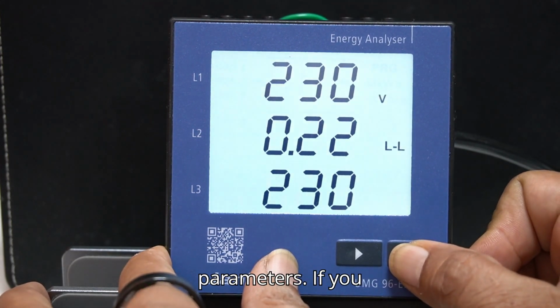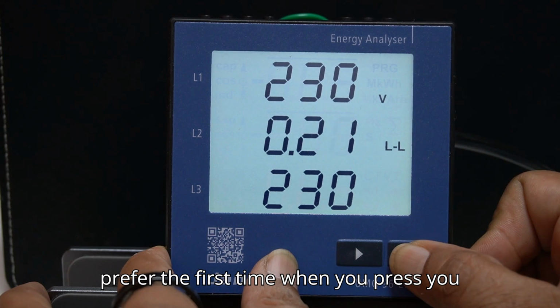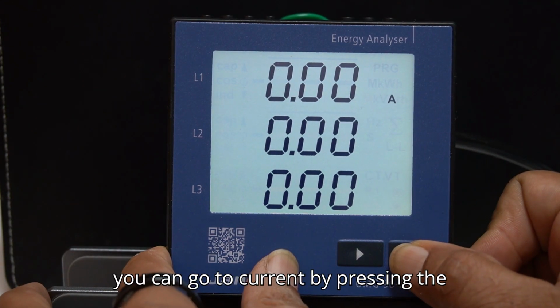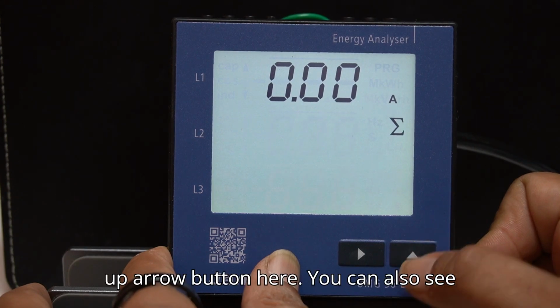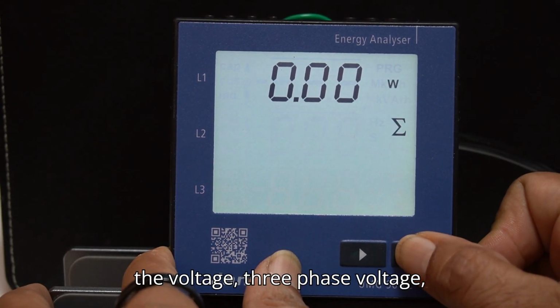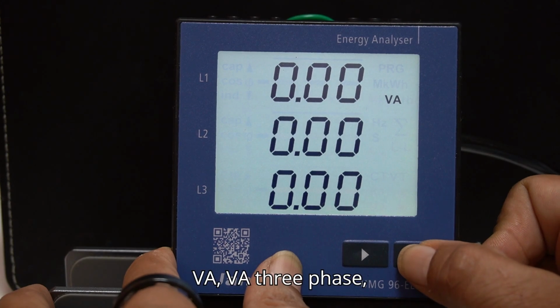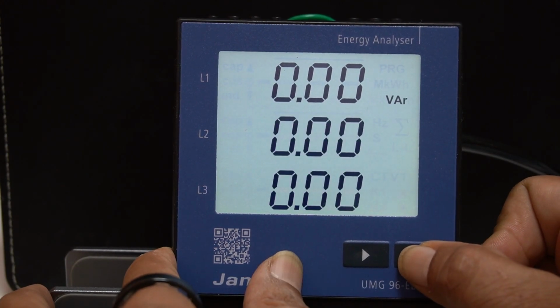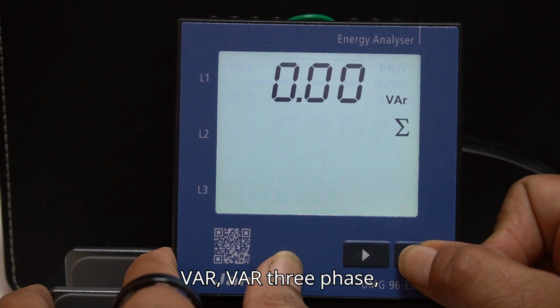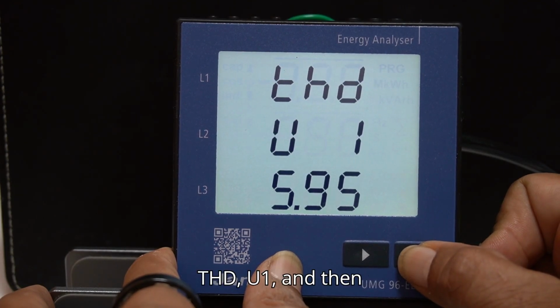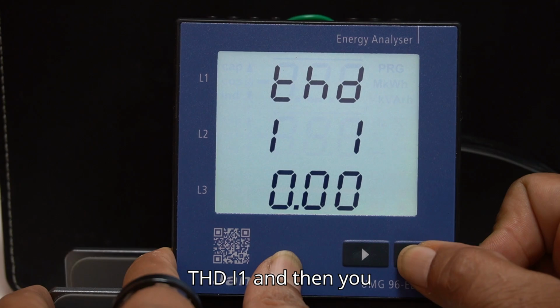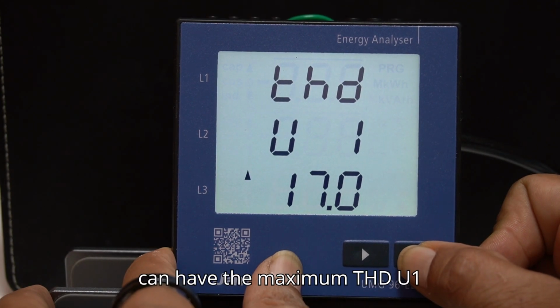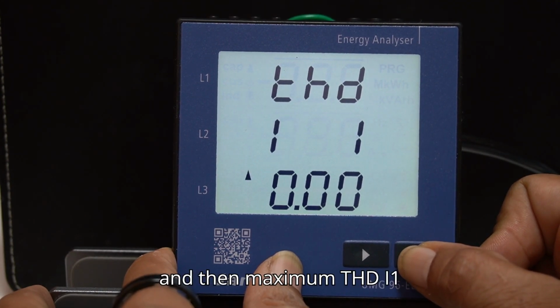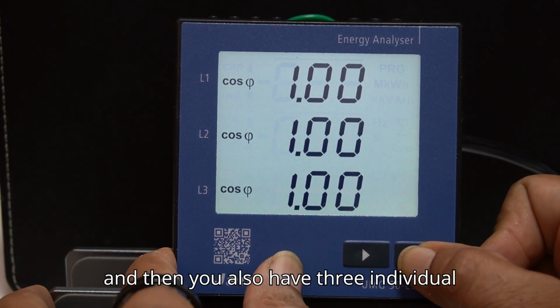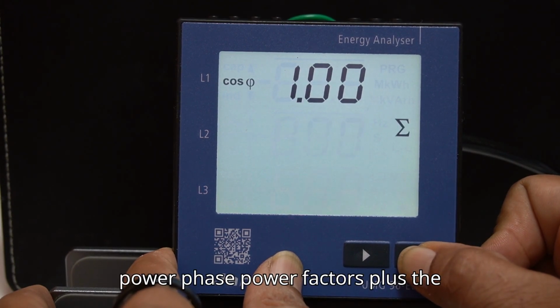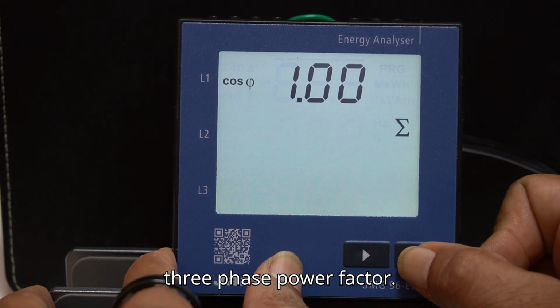Then you can use the up arrow button on the right side to navigate to the other parameters. The first time you press it, you get the backlit display as well, and then you can go to current by pressing the up arrow button here. You can also see the wattage, three-phase wattage, VA three-phase, VAR three-phase, THD U1, THD I1, and then the maximum THD U1 and maximum THD I1, and then you also have the three individual phase power factors plus the three-phase power factor.